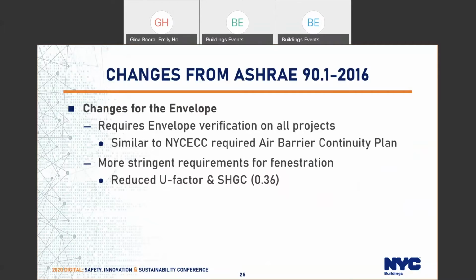So those are all the changes from the state code in the ECC compliance path. Now I'm going to talk about the changes that originated from ASHRAE 90.1 2016. Also, as a reminder, I didn't talk about this in the beginning, but when you have a commercial building following the energy code, anything over 4 stories is required to comply with the commercial provisions. Any occupancy that's not residential also has to comply, at any story in height. There are 2 compliance paths. There's the compliance path for ECC, those are the changes I just went over. An alternative compliance path is to follow ASHRAE 90.1. So the changes that I'm going to talk about are in this alternative compliance path. Either one is allowed for code compliance.